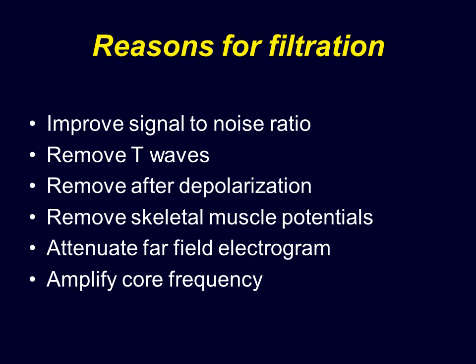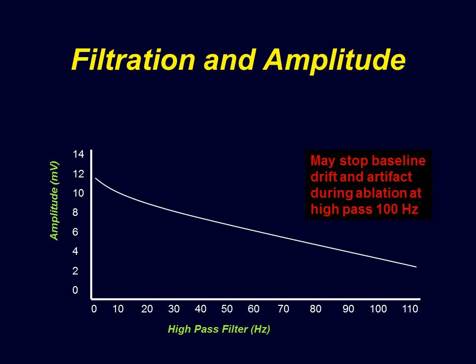Why do we filter? We want to improve the signal-to-noise ratio, remove T waves, remove after-depolarizations in case of pacemakers, and remove skeletal muscle potentials. We want to attenuate far-field electrograms and amplify the core frequency of interest. Filtration may also stop baseline drift — particularly if your lab is not well grounded, you could have baseline fluctuation during ablation, and the high-pass filter can be raised from 30 to 100 to address this.